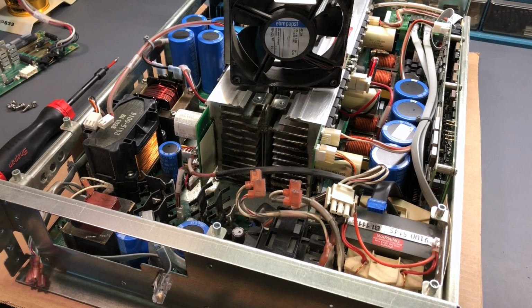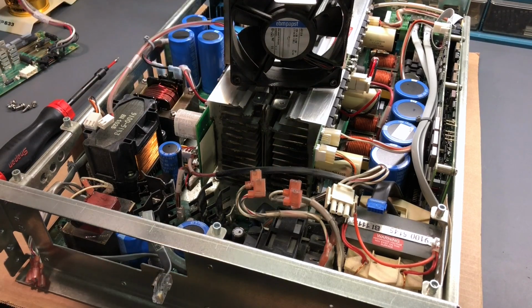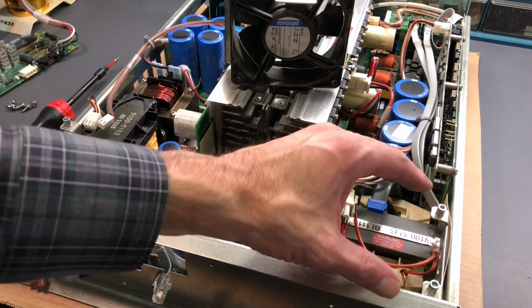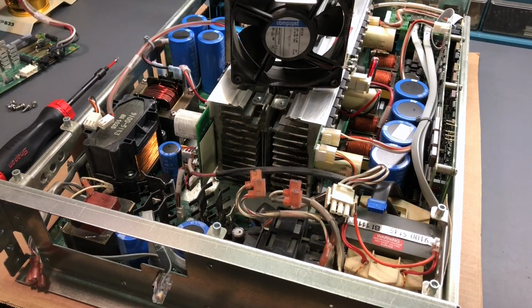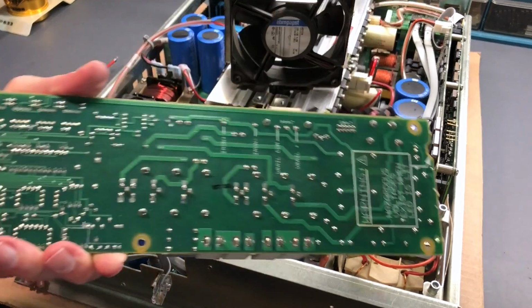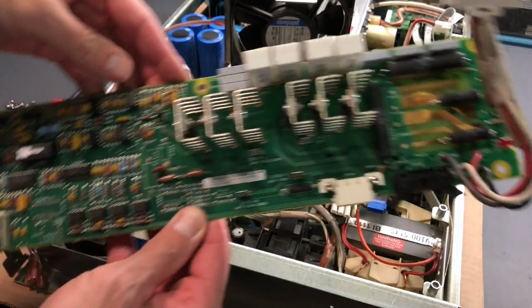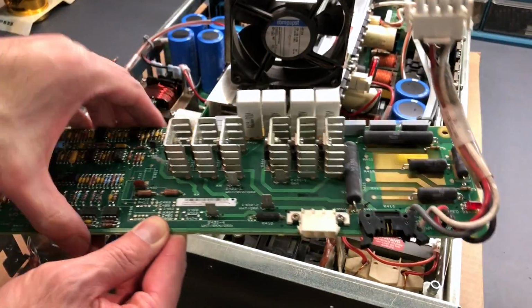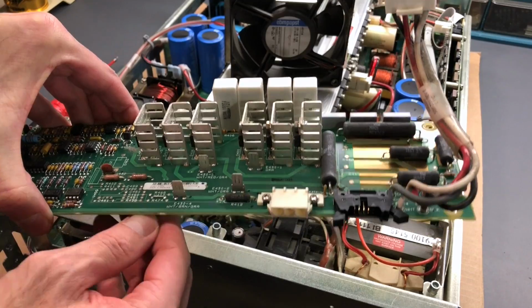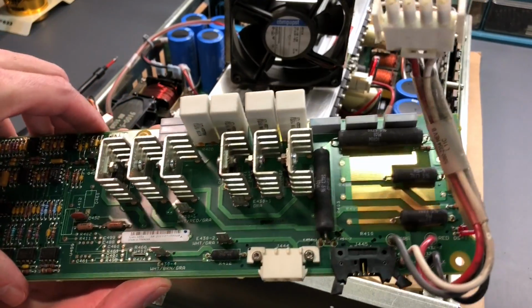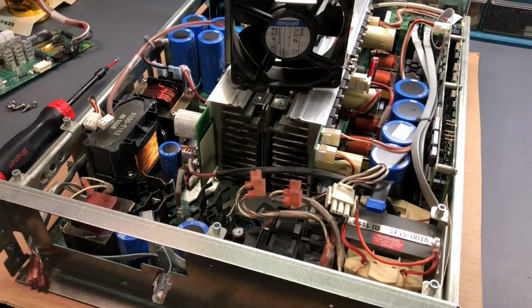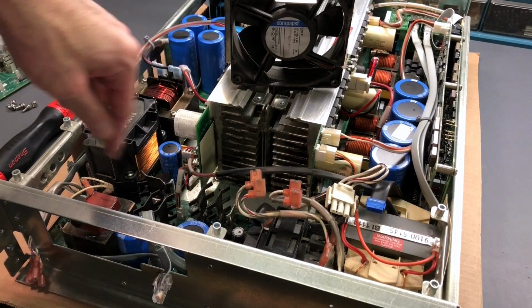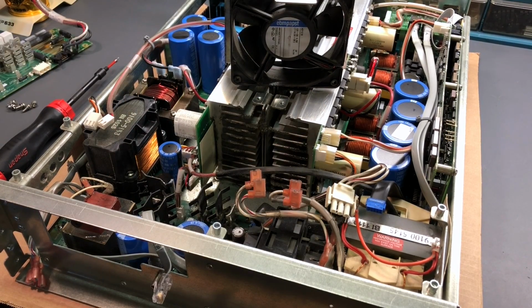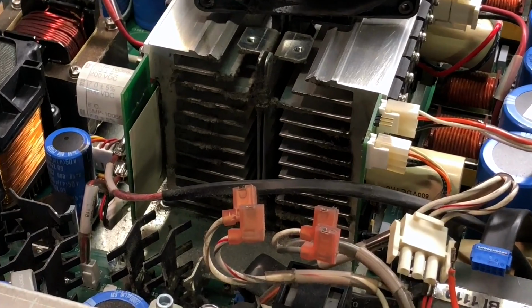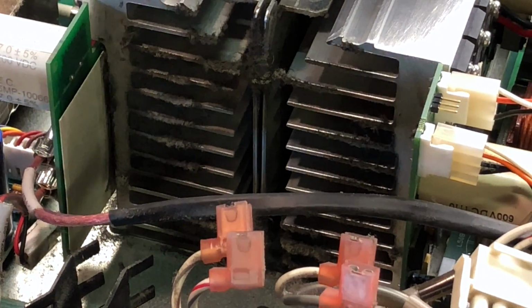All right, the cleaning and disassembly is underway. So you can see the fan is sitting up here. I've got it removed. The DC rail assembly, that circuit board that sits right here, I've removed that. It's sitting over here, so we were seeing it in this position, but when you flip it over, you can see the components on the other side. It was extremely dirty. All these heat sinks had lint and dust hanging all over them, so I've started cleaning on that. It needs a little bit more cleanup, but it's coming along nicely. And with that removed, it gives access down to this lower area here, which is completely packed with lint and dust as well. And in fact, you can get an appreciation for how much lint and dust has accumulated if I zoom into this heat sink and grab a flashlight real quick here.